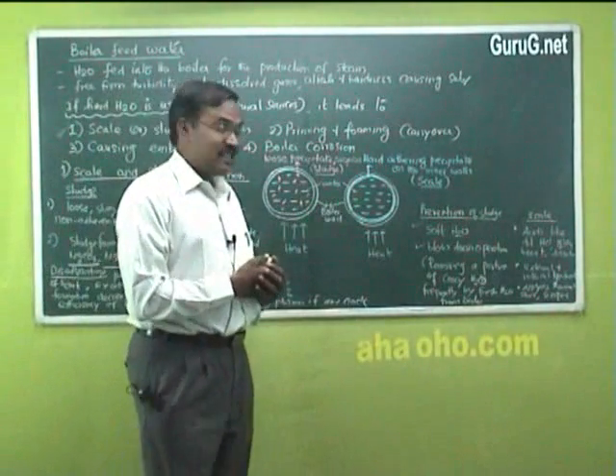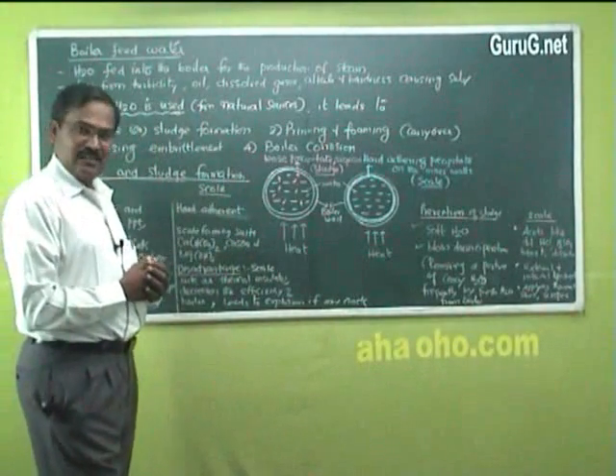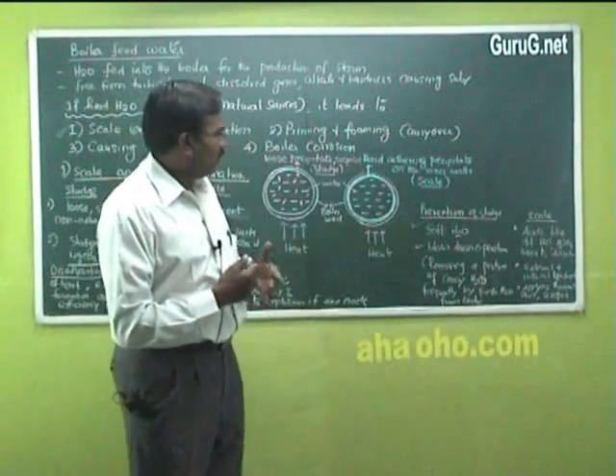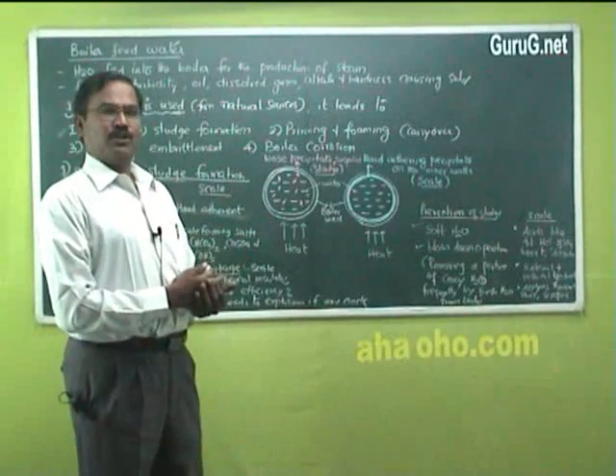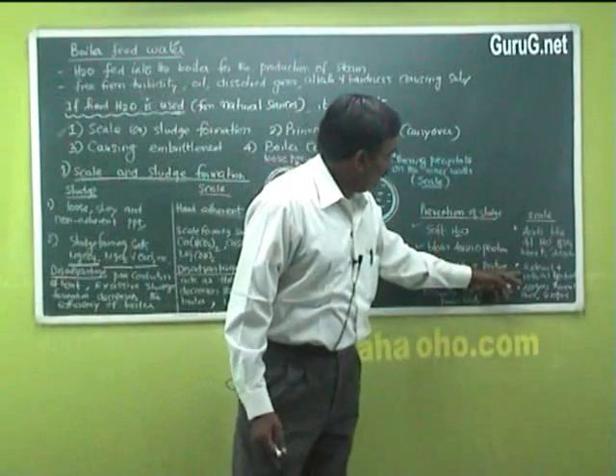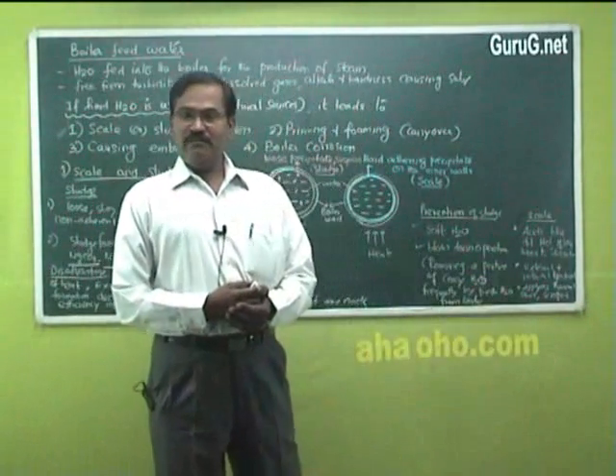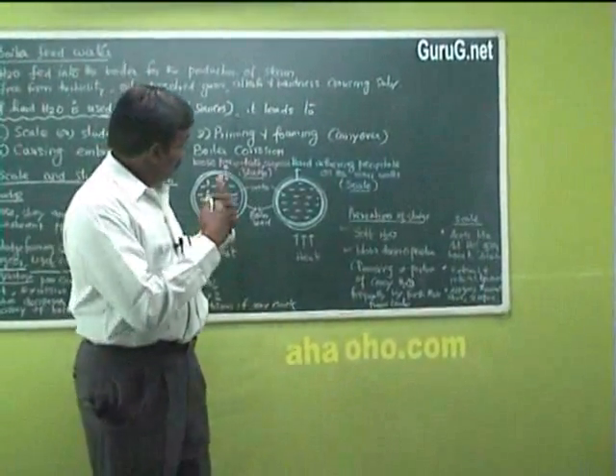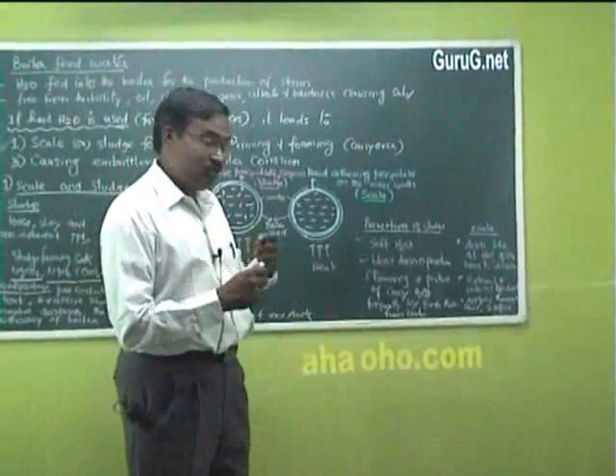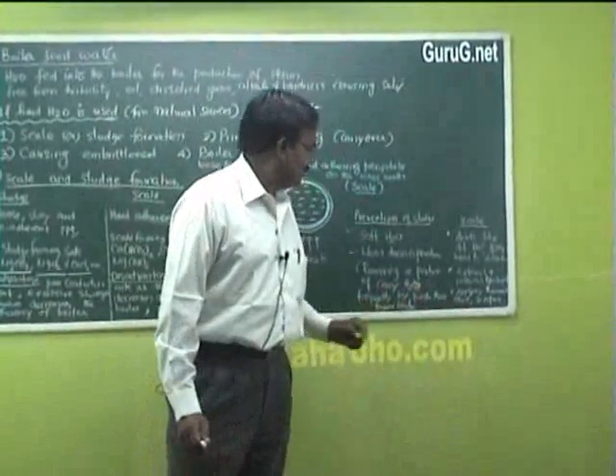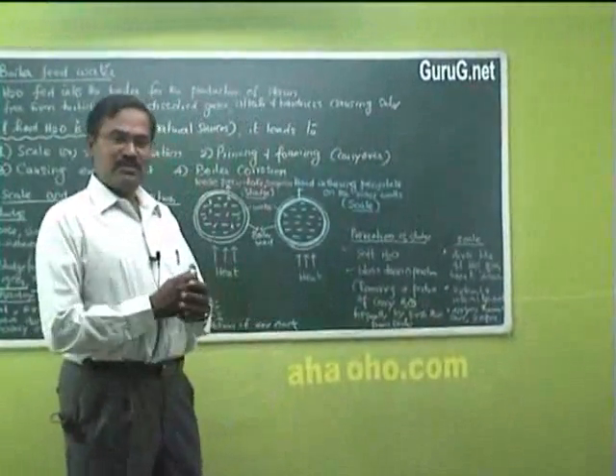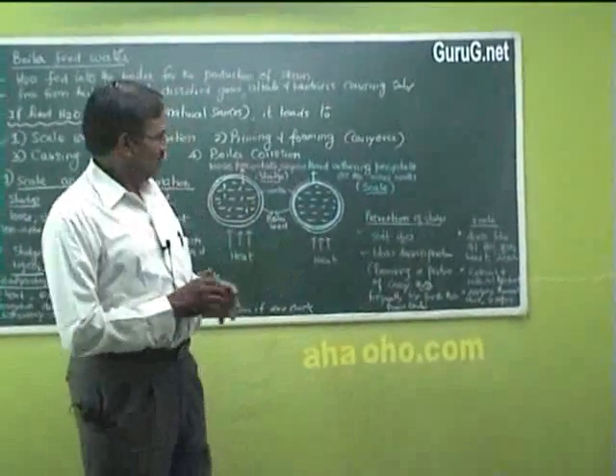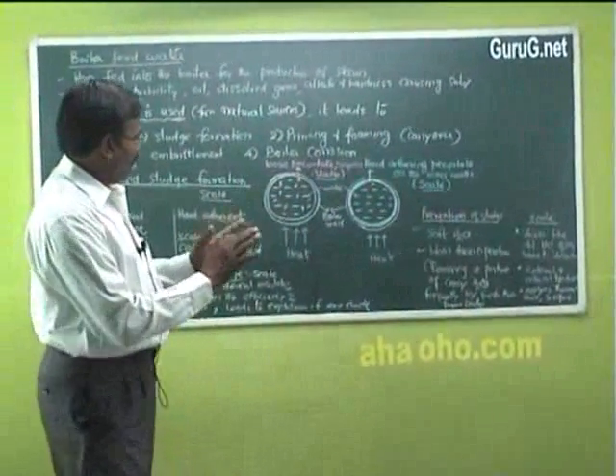For scale formation, scales are readily soluble in acid, so we can dissolve the scale periodically. We also have pre-treatment before water is taken for the boiler, either external or internal treatment. If scale has already formed, it can be removed by applying thermal shock, or by using scrapers or wire brushes. This is how scale formation can be prevented.